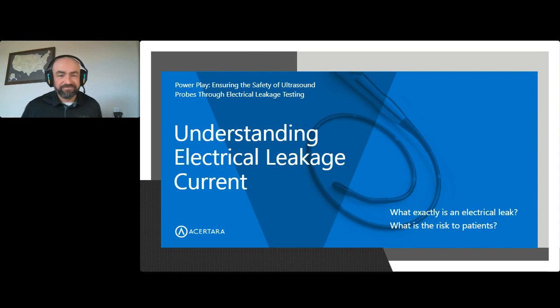Electric leakage, what is that, and what is the risk to the patient? Electric leakage is a breakdown in the insulators between the electrical signals and power that is going to the probe and the patient. Those insulators are typically your lens and your insertion tube. Those kinds of patient interface contact points are where you worry about this electric leakage going into the patient.